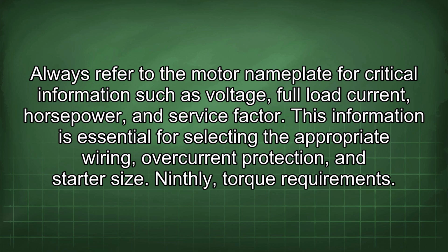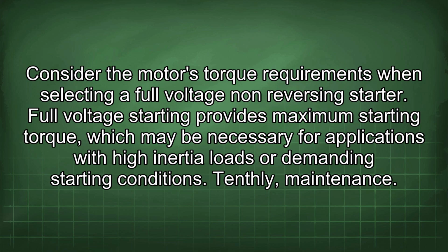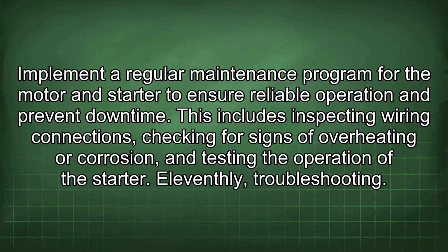Ninthly, torque requirements. Consider the motor's torque requirements when selecting a full-voltage non-reversing starter. Full-voltage starting provides maximum starting torque, which may be necessary for applications with high inertial loads or demanding starting conditions. Tenthly, maintenance. Implement a regular maintenance program for the motor and starter to ensure reliable operation and prevent downtime. This includes inspecting wiring connections, checking for signs of overheating or corrosion, and testing the operation of the starter.